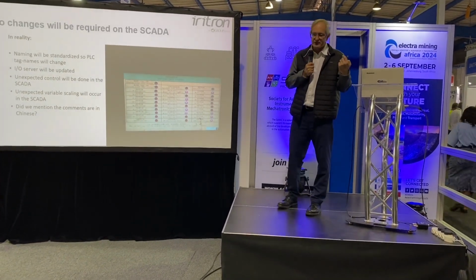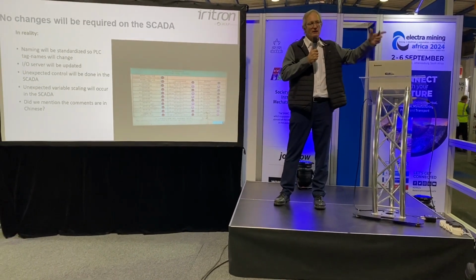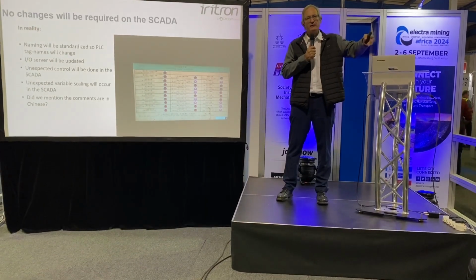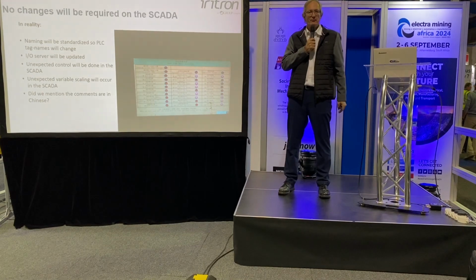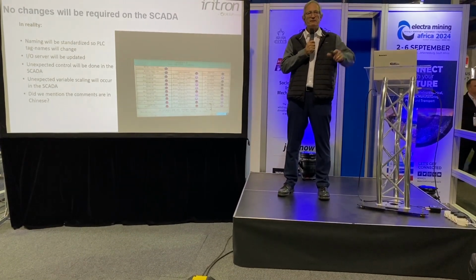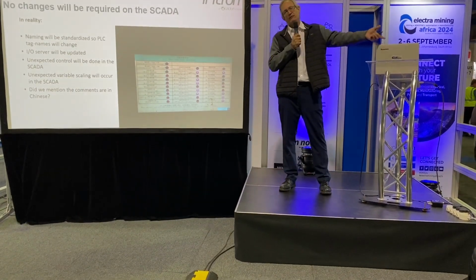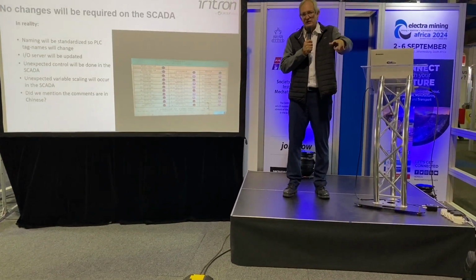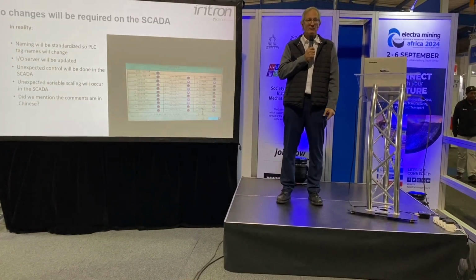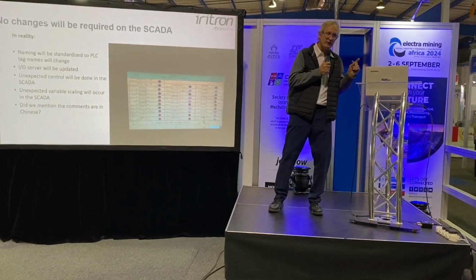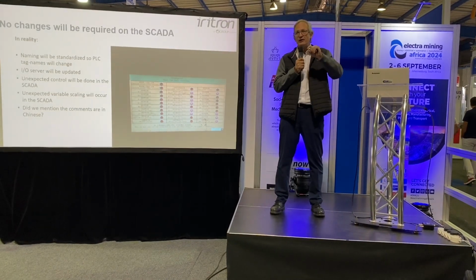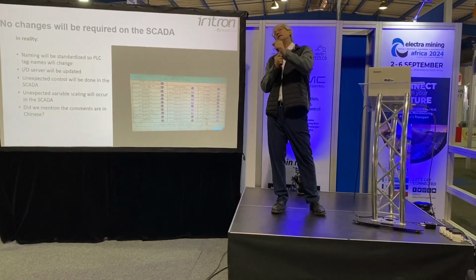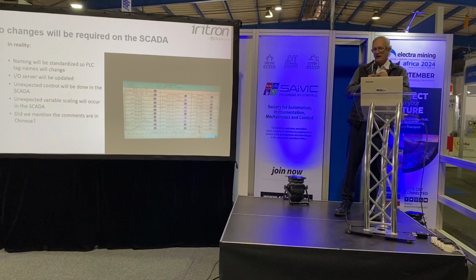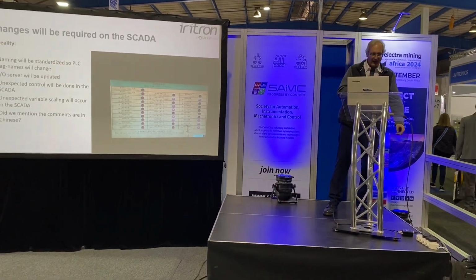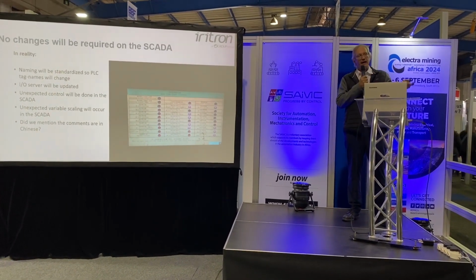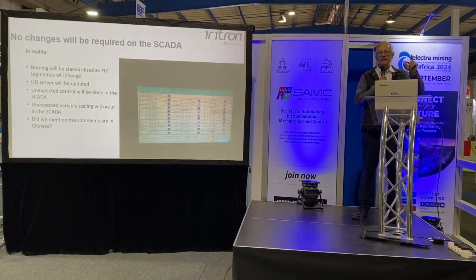And then you'll also find that in your SCADA system, when they commissioned the plant, the instrument that they had in the field sent the information directly into the PLC, and the PLC did the scaling. But they changed the actual equipment, the actual meter, 5 years ago, and at the time when they did that, there was no PLC guy available to make the change. But there was a SCADA guy. So the SCADA guy used the PLC code and changed the ratios, right, to make the instrument display accurately in the SCADA system. Those are the type of things you only find out when you're commissioning on site. Right? Lots of sleepless nights just to find out that's why we're not getting the correct signals in, because in the SCADA we're actually dividing it by 1,000.